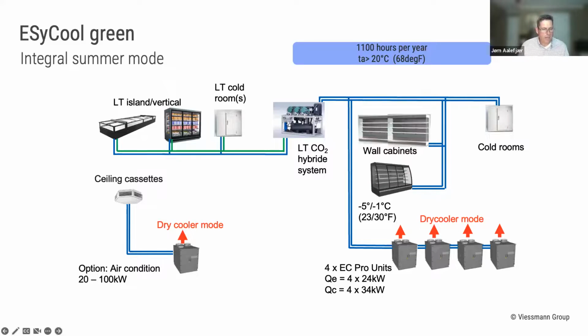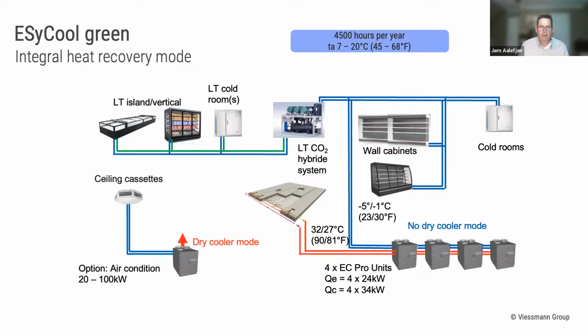It goes without saying that there's no really energy saving in this mode. This is where we are least efficient. We need to be able to use the heat somehow. To dissipate it into the air doesn't give the savings you're looking for. So in, let's say, the areas of the year where the temperature is between 45 to 68 degrees Fahrenheit, that's approximately 4,500 hours per year. Here we start using the heat. You don't use the heat pumps in dry cooler mode. Here I just put in, we use it for heating the floors. We can do additional things. We can put in connection also to the normal climatization, air-based climatization for the store or the building. Again, any other way you want to use the heat, we can comply.